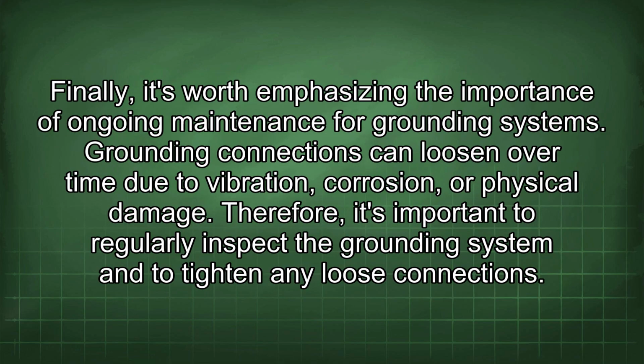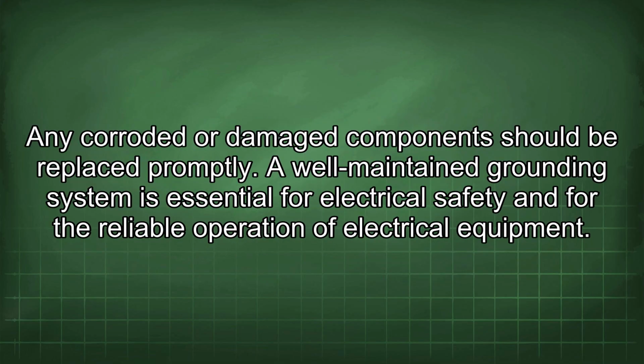Finally, it's worth emphasizing the importance of ongoing maintenance for grounding systems. Grounding connections can loosen over time due to vibration, corrosion, or physical damage. Therefore, it's important to regularly inspect the grounding system and to tighten any loose connections. Any corroded or damaged component should be replaced promptly. A well-maintained grounding system is essential for electrical safety and for the reliable operation of electrical equipment.